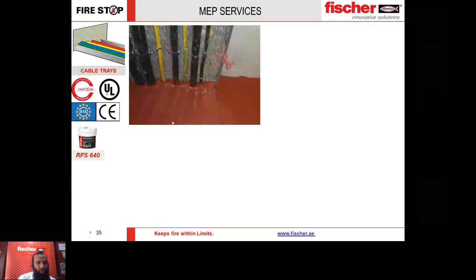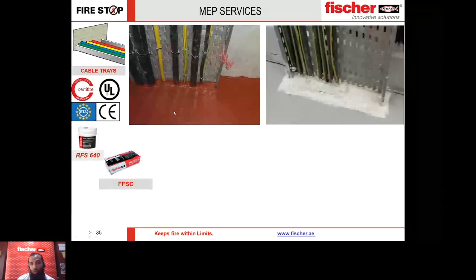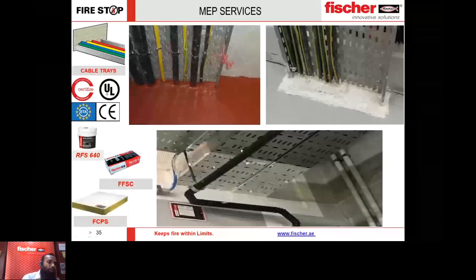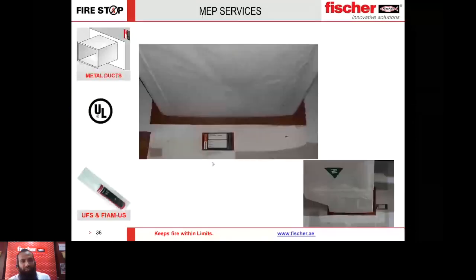For electrical services and cable trays, the solution is mineral wool backing with RFS 640 at just 3 mm thick. You can also use a mortar at 65 mm thick to achieve a 2-hour fire rating, but RFS is preferred — applied with a spray machine or scraper. The easiest application-wise is our FCPS board, which can be used for cable trays without overcoating.